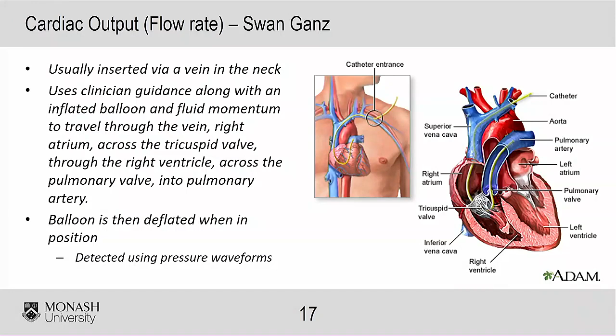So the way we do that is using the equation on the top here. So we include the volume of the injectate, the temperature of the blood, which we can usually assume is a certain temperature. This might be an assumption. In cases where it might be a little bit different, the clinician can also put that in. We have to put in the temperature of the injectate, and this is usually controlled before they put it in, so we know what that is. The specific gravity of the injectate is something that is set. We know what that is. And same thing with the specific heat, because we know what the fluid is. The specific gravity of blood and the specific heat of blood are also known constants. So essentially we only have to put in a few parameters, and then it uses the area under the curve to essentially calculate what the cardiac output is.